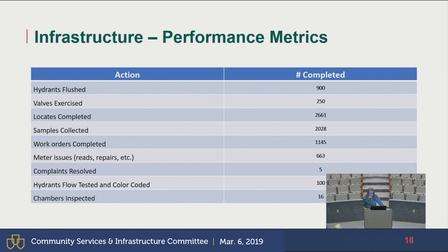address the remaining 100 hydrants and did flow testing and color-coded. So when you drive down the streets, you'll see at nighttime when you're driving, it lights up like Christmas. That is for fire. It's to help the firefighters know how much flow they're going to get from each one. So it is a safety factor, but it also lets our staff know as well that the hydrants have been tested, they're operational, they're flowing, and they're flowing at a specific amount. So it is a regulatory requirement, but it's also a safety. So we've highlighted it from that point. And we inspected 16 of our chambers.